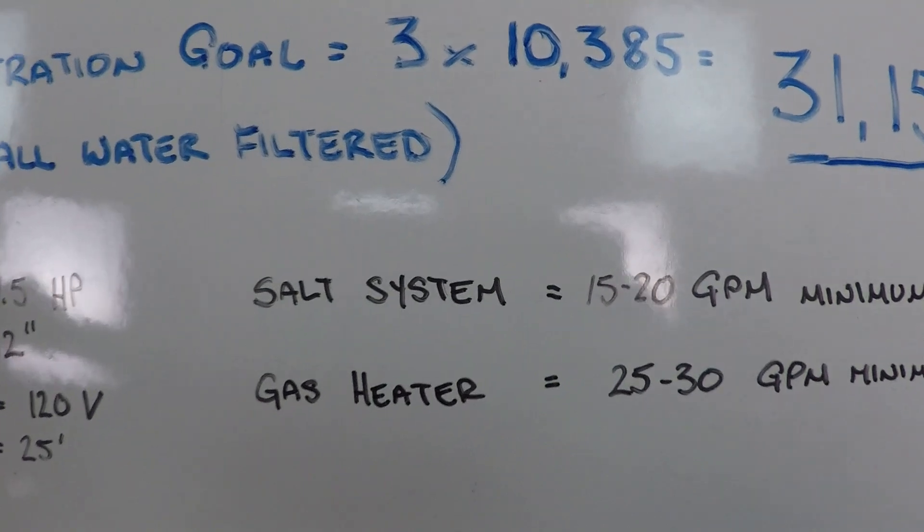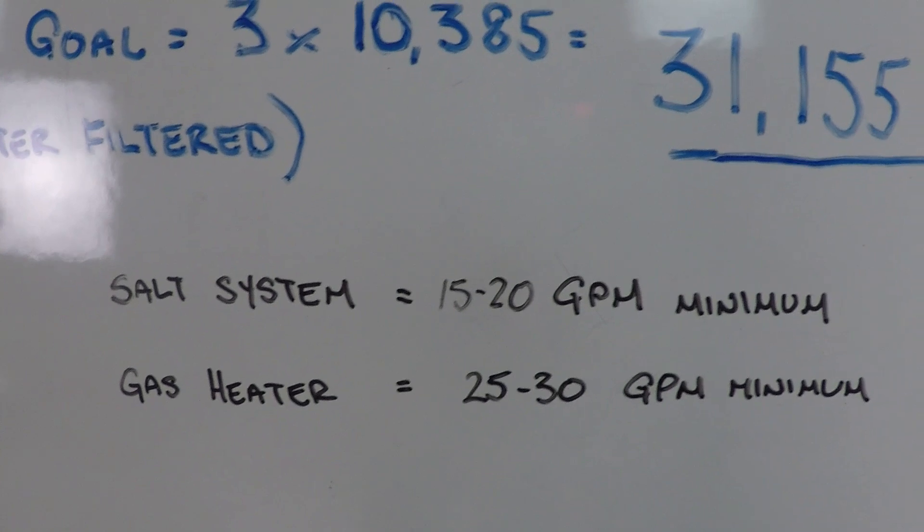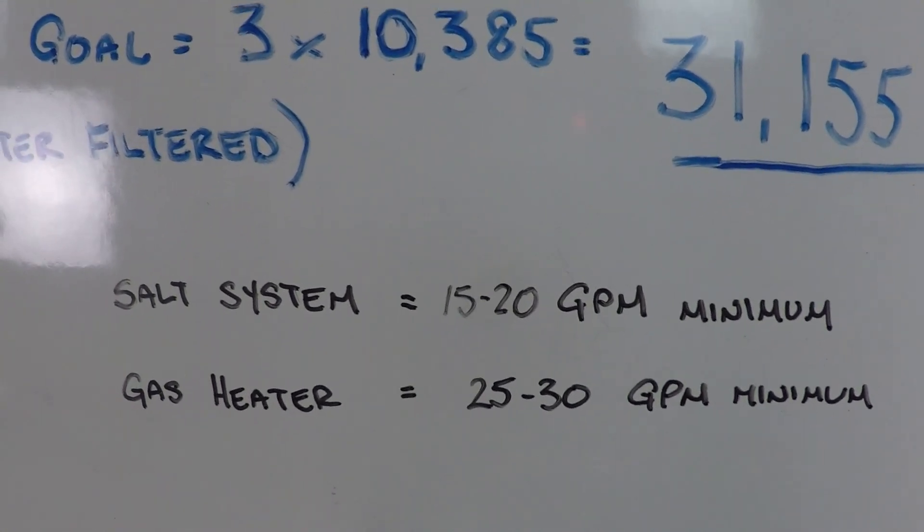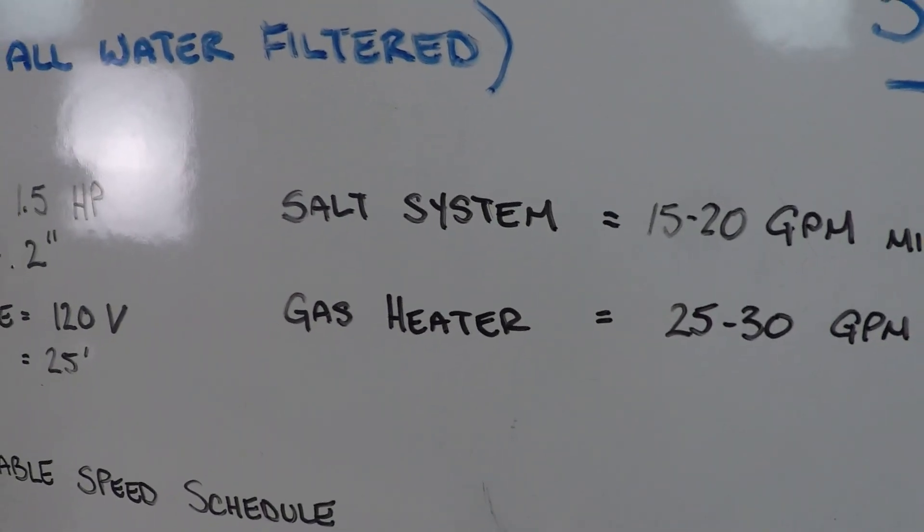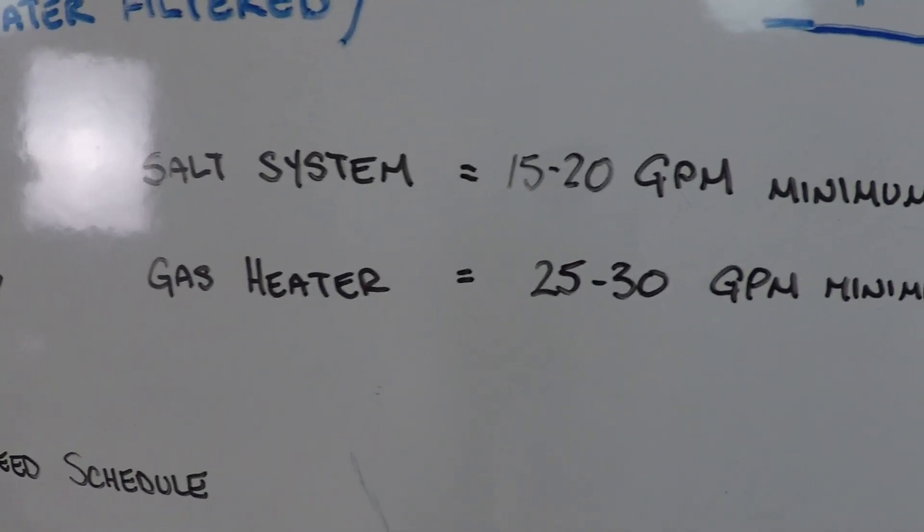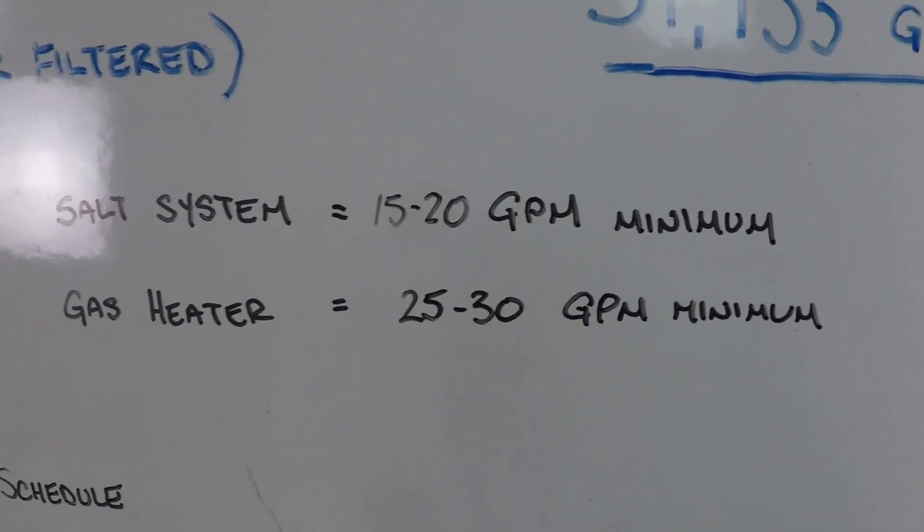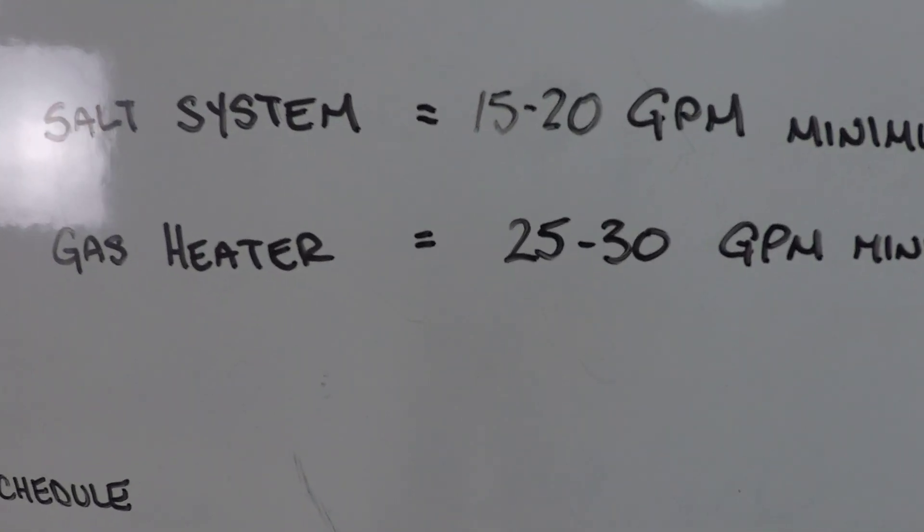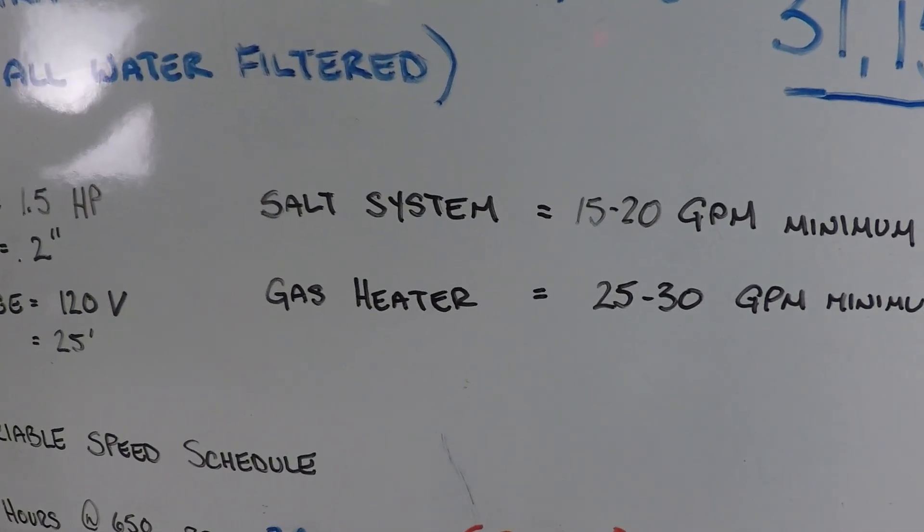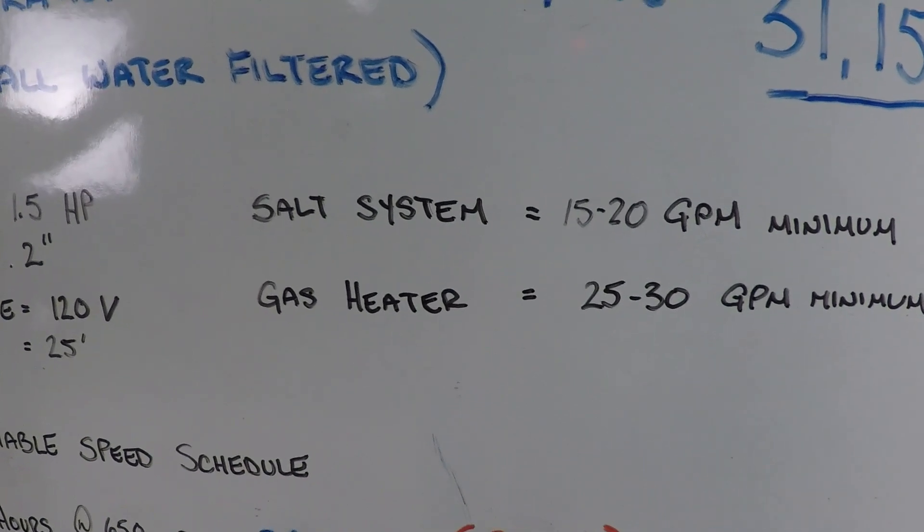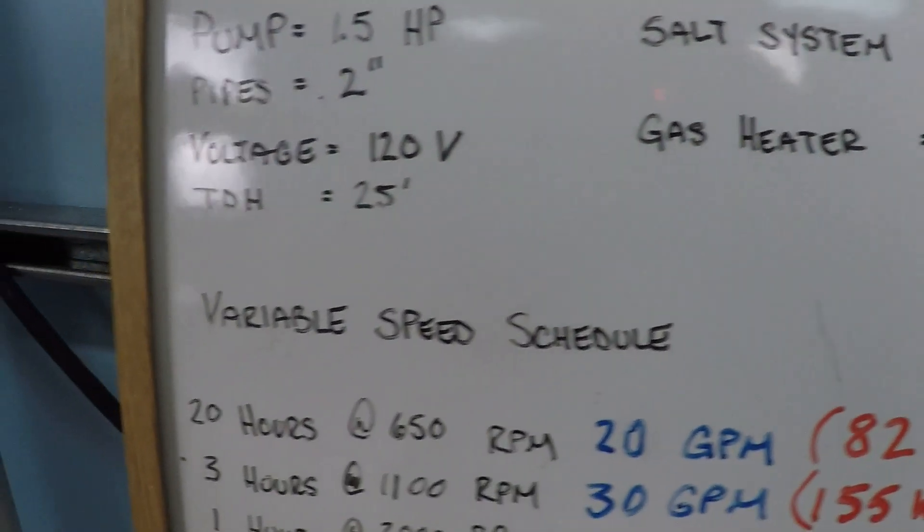Some other stuff that we need to consider: What if there's a salt system on this pool? A salt system is going to need, on average, 15 to 20 gallons per minute in order to operate. Same with a gas heater. If you had a gas heater, on average, you're going to need 25 to 30 gallons per minute minimum in order to operate, maybe a little bit more than that for some of the larger heaters. These are the things you need to consider when deciding exactly what RPM you're going to be operating this pool at. Let's break that down further.